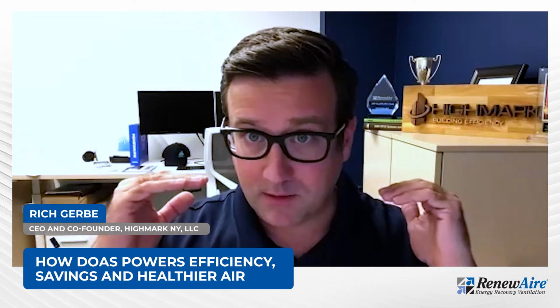But a system that's got a properly designed outdoor air system and is giving you that consistent temperature is going to reduce your energy consumption, and boy, that indoor air quality is going to be at such a great starting point. So, a very good point, and I appreciate you guys bringing that up. Yeah, you're right about some of these very highly efficient VRF type systems, or chilled beams or radiant panels. They do not have any dehumidification capability.